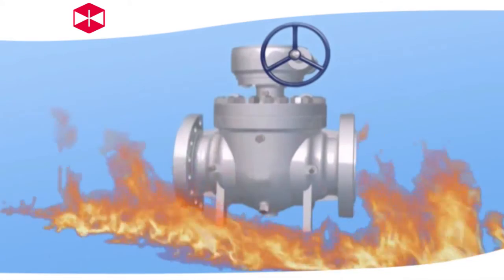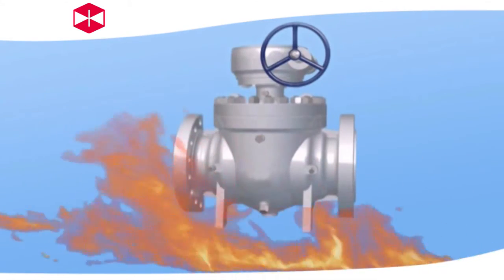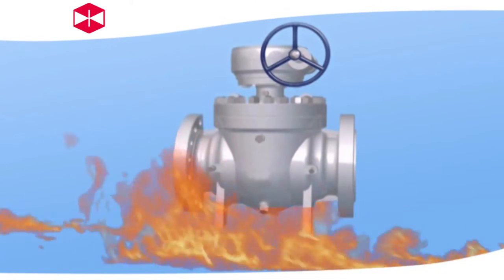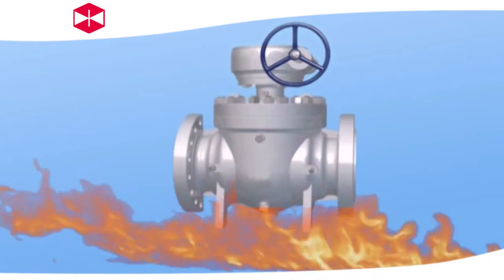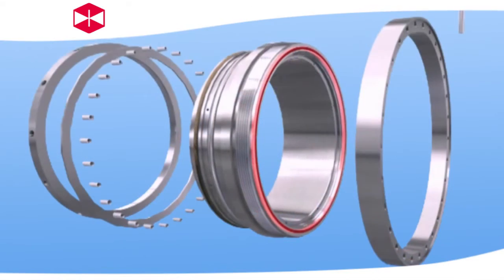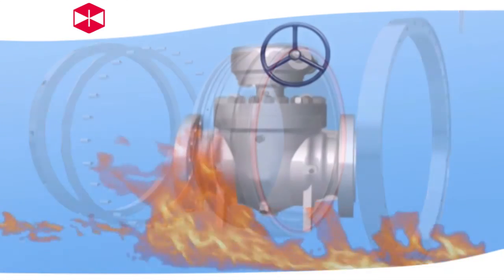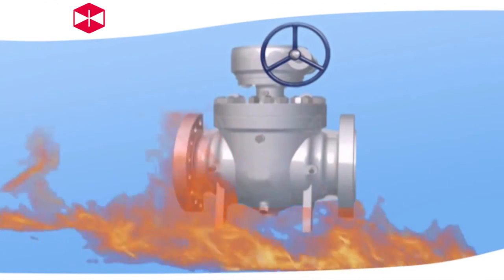There is some metal fire protection sealing face set on the back of non-metallic seal ring of the ball valve produced by VARK. And the connected seat ring and the grease injection valve installed outside of the body. Once the seal ring is burned, the ball will contact with the metal sealing face on the seat directly. And injecting sealant by grease injection valve will realize urgent sealing to prevent medium leakage.